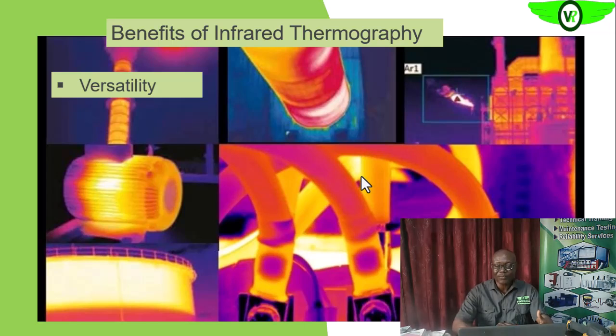So as a fault is developing on the bearing, definitely the heat emitted from that bearing will increase, which will eventually be transmitted onto the housing, which we will see clearly in the thermogram. So it is a very versatile technology. It even has both security and medical applications. So we'll see all of this.